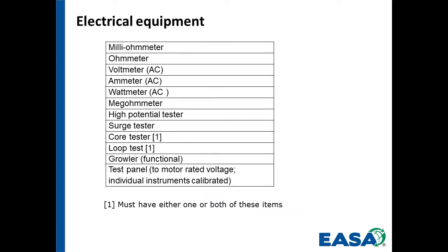Equipment that's needed on the electrical side. Things like a milliohmmeter and ohmmeter. Some of these are relatively common in the service center: ohmmeters, voltmeters, ammeters, and so on. Others are not as common, perhaps. A milliohmmeter, a bridge-type device, has 4 leads for measuring low resistance down into the milliohms, sometimes even into the micro-ohm range, and we need that especially for larger windings, for lead-to-lead resistance.